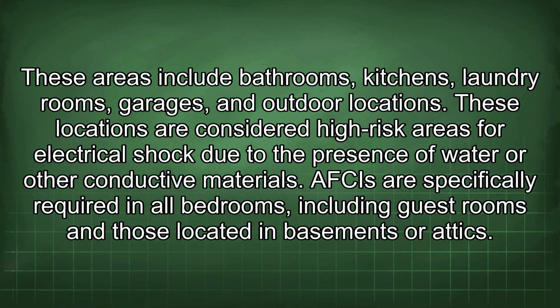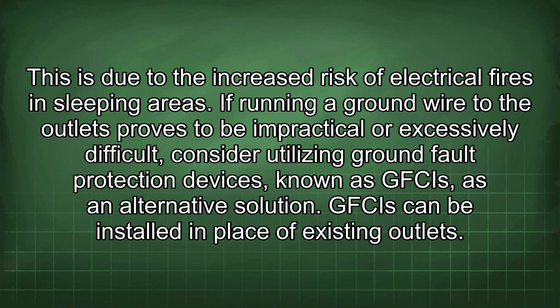AFCIs are specifically required in all bedrooms, including guest rooms and those located in basements or attics. This is due to the increased risk of electrical fires in sleeping areas. If running a ground wire to the outlets proves to be impractical or excessively difficult, consider utilizing ground fault protection devices, known as GFCIs, as an alternative solution. GFCIs can be installed in place of existing outlets.